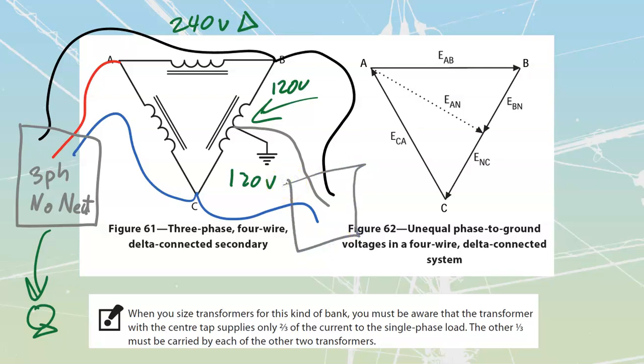So you're going to come off that transformer, you're going to feed lines to these ones over here. And inside of that panel, you are then going to have the option to do single phase. It will have to be a single phase panel. 1-phase panel. It's obviously going to have a neutral bus that this is going to go on. This would become your line 1 and your line 2. Although they aren't line 1, line 2, it's not phase A, B, and C. It's a single phase line 1, line 2. And so you would be able to distribute all of your single phase loads out of that panel itself.